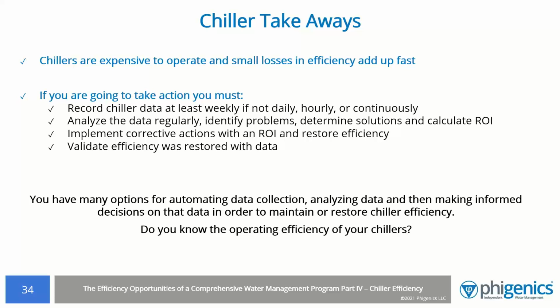To wrap this up, chillers are expensive to operate, and small losses in efficiency add up fast. If you're going to take action, you must record chiller data at least weekly and preferably daily, if not continuously. You must analyze the data regularly, identify problems, determine solutions, and calculate the ROIs in order to make informed maintenance decisions. Then, of course, you must take action and implement the maintenance or repair actions with an ROI and restore efficiency. Lastly, you must always validate or measure if the efficiency was actually restored.